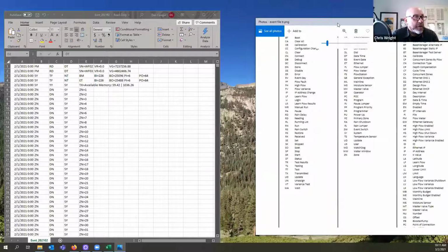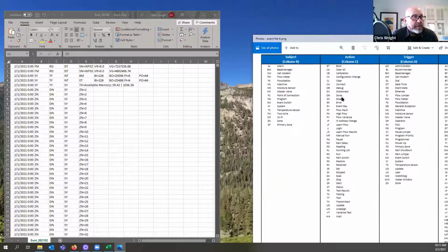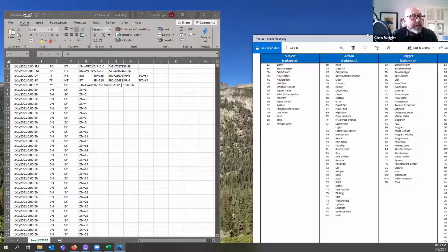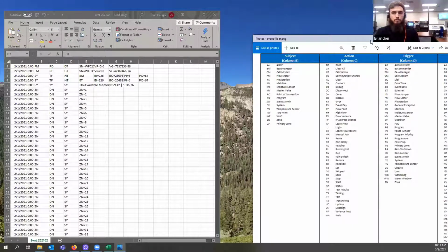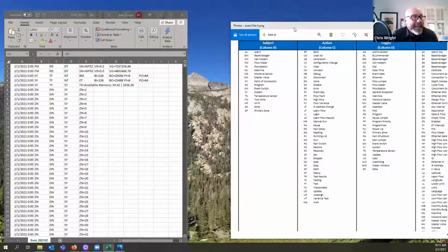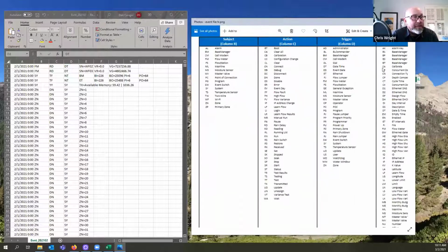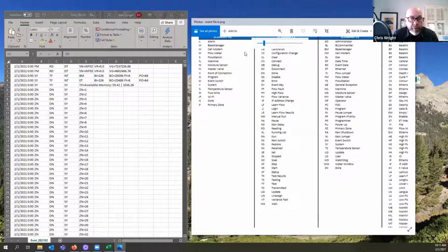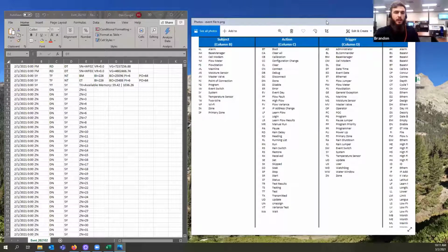And one thing that I've noticed too, looking at the CSV file, it's showing 2/1/2021, and then the time stamp is all zeros. So this is at midnight, what the status was for all of the devices connected to the controller, correct? Correct. So yeah, you've got zones 1 through, I don't know how many zones you have configured on your demo controller, Dan, but it's showing you ZN is zone, and it's showing you what the status is for that zone at midnight for every zone. That's why there's so many zero timestamps. Exactly. Right. If there's multiple lines, then it'll expand out like that.